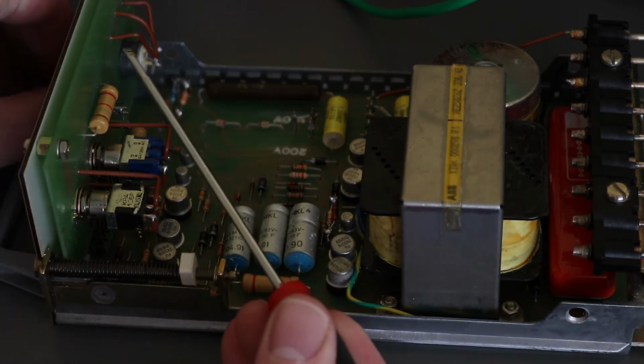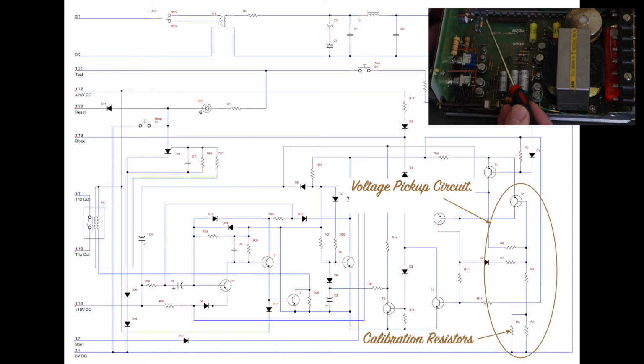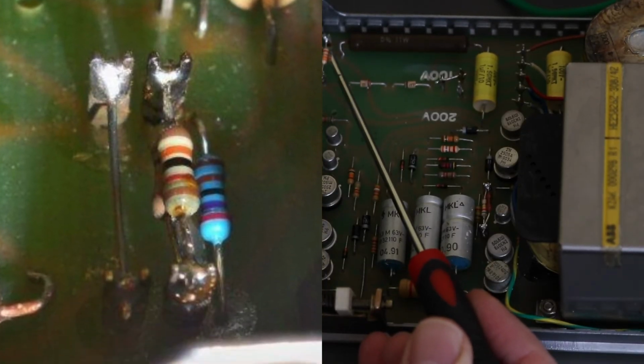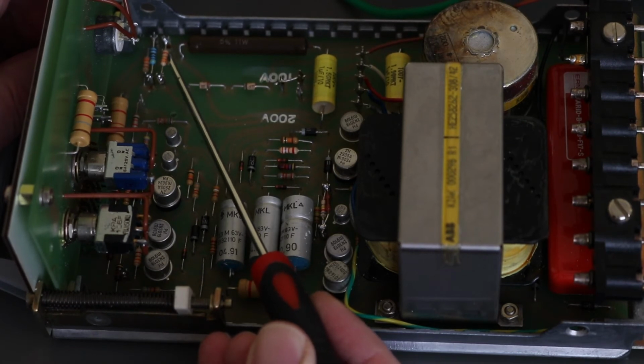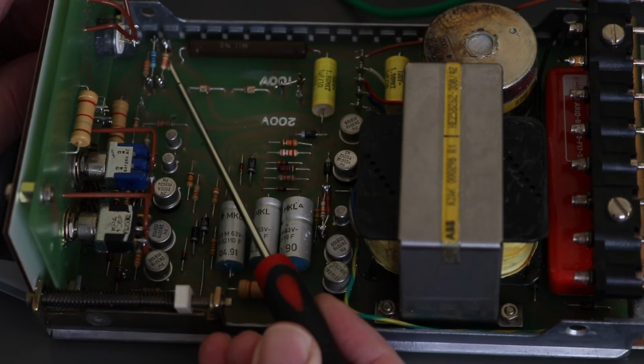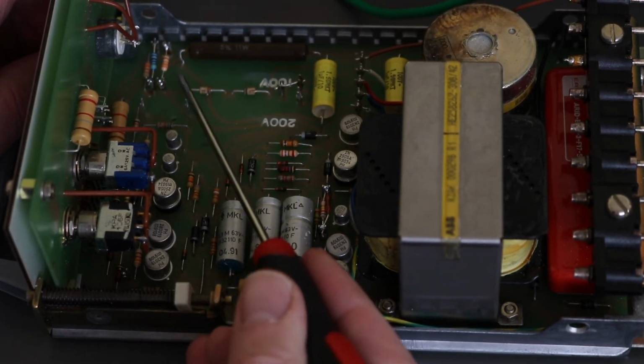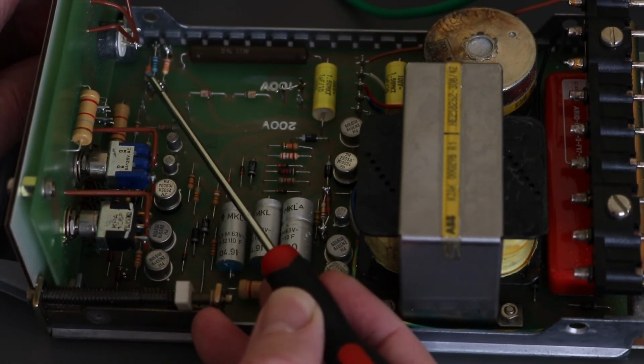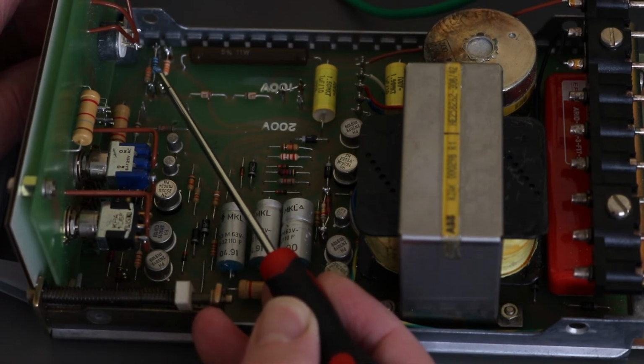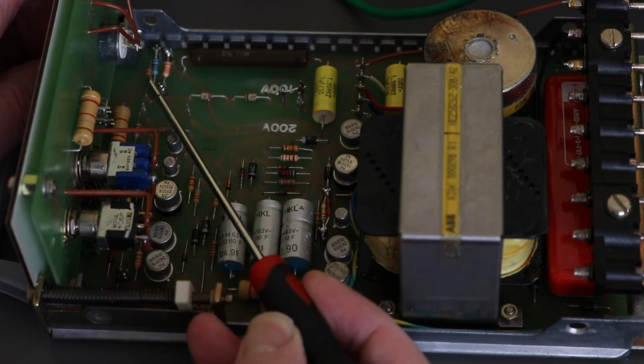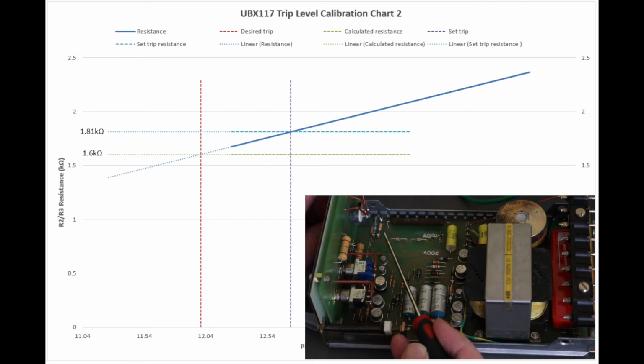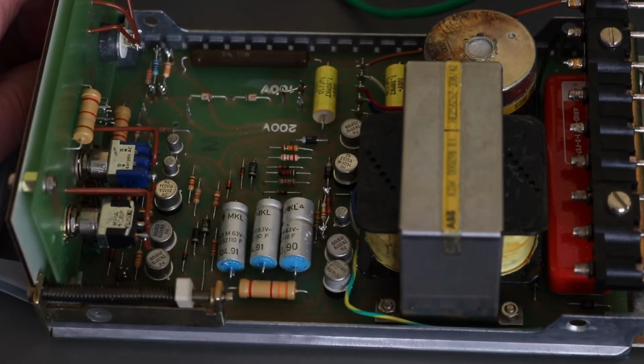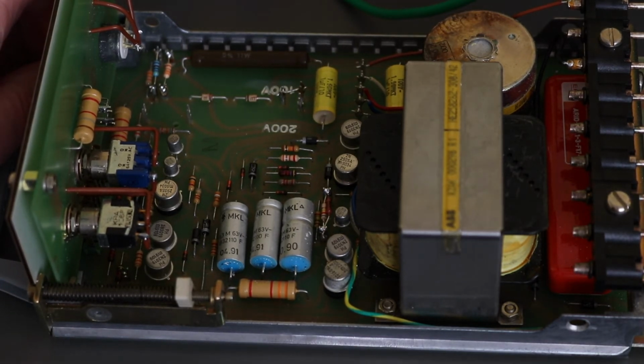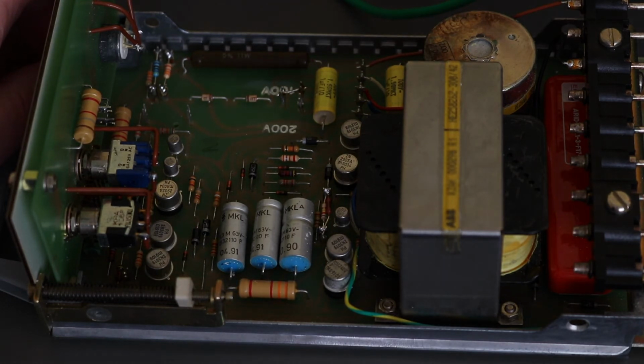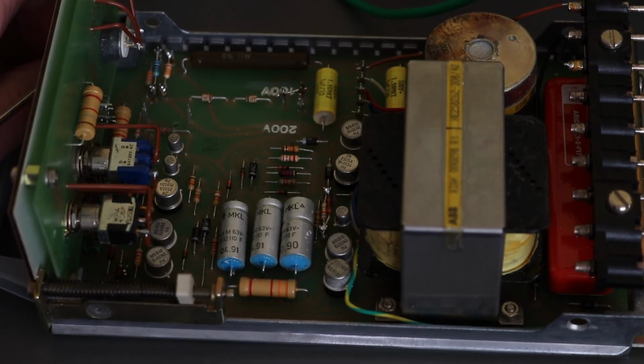So on the voltage detection, or the pickup voltage, that's calibrated by this set of resistors up here. For some reason previous relays I've repaired haven't had this resistor in there, so I don't know quite why this one is in. It's a slightly different part of the circuit and lifts the base voltage up to the tripping transistor, so I've actually left that value as I found it and just recalibrated based upon the new set of readings that I was getting. Unfortunately that means I've had to generate a new calibration plot because the relay operates slightly differently with this resistor in place. And for voltage pickup I will take minus 0% up to plus 10% of the setting that's on the front of this relay.